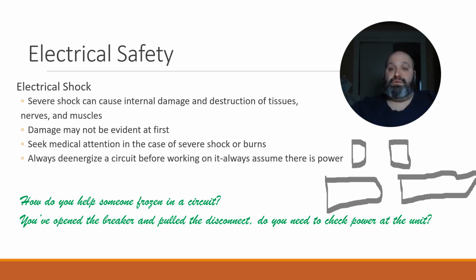So I had a no cooling, AC not cooling call. Okay, walk up to the condensing unit, and it's not doing anything. And the contactor's chattering away. Obviously, that's bad. I'm going to go the extra mile and make sure I test the capacitor. More than likely, it's bad too, but it's definitely worth checking. So, pull this disconnect and start unwiring the capacitor, and got grabbed by the current.